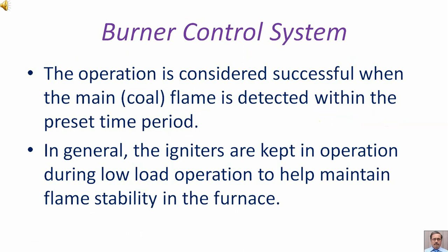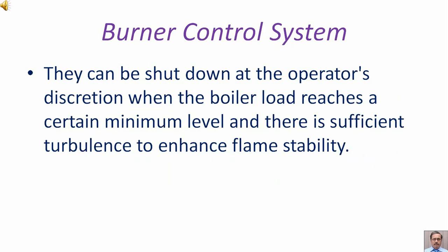In general, the igniters are kept in operation during low load operation to help maintain flame stability in the furnace. They can be shut down at the operator's discretion when the boiler load reaches a certain minimum level and there is sufficient turbulence to enhance flame stability.